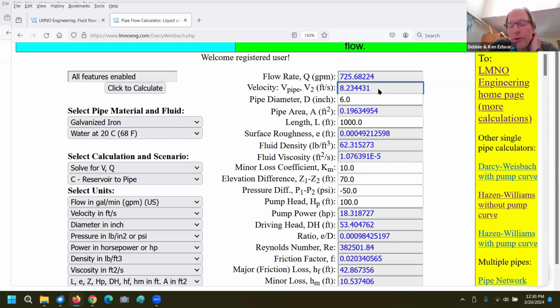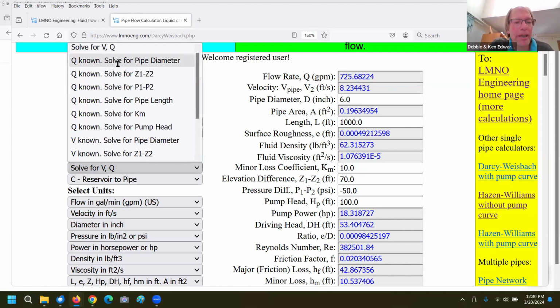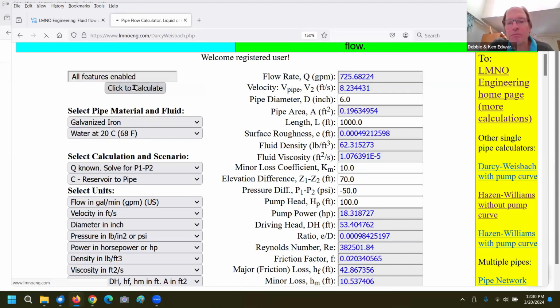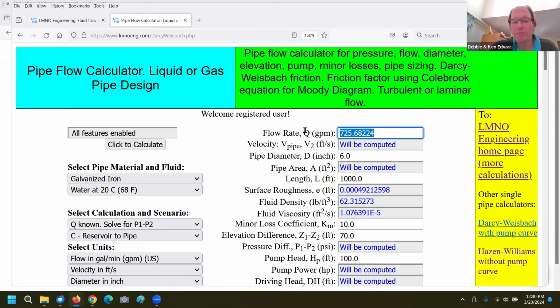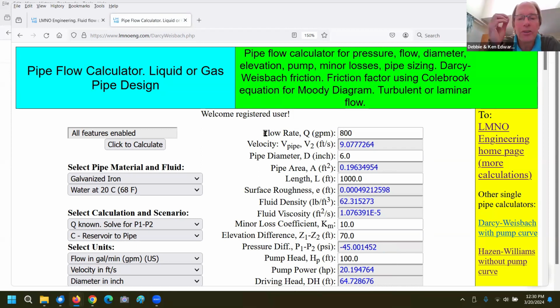And so, a lot of our customers want to know a pressure difference between 2 locations in a pipe. So you can select, maybe solve for, if you know your flow rate, you can solve for a pressure difference. So maybe you put in your flow rate, just going to key in a round number here. So maybe you've got 800 gallons per minute, and this is US gallons per minute. Be careful if you're in a country that uses imperial gallons per minute, because there is a unit conversion there.